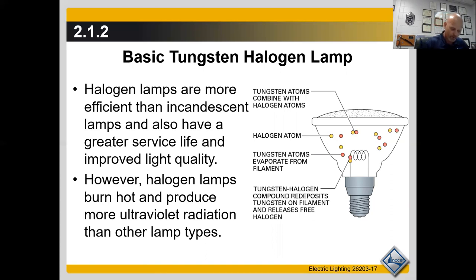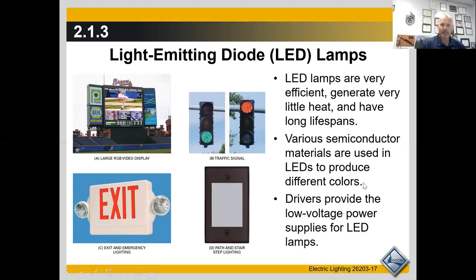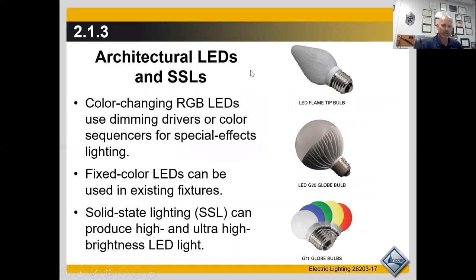Section 2.1.3 discusses LEDs — light emitting diodes — which are rapidly gaining popularity. Some of the latest ultra-high brightness LEDs can output light with an illumination efficiency of 100 lumens per watt at 350 milliamps. They generate little heat and have long lifespans. Various semiconductor materials are used to produce different colors, and drivers provide the low-voltage power supply for LED lamps.